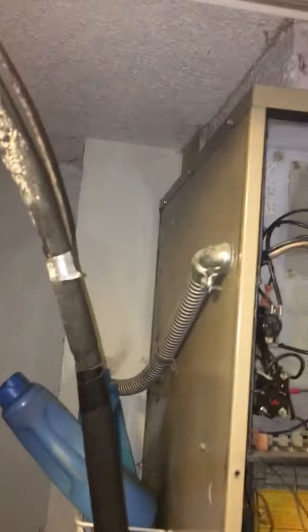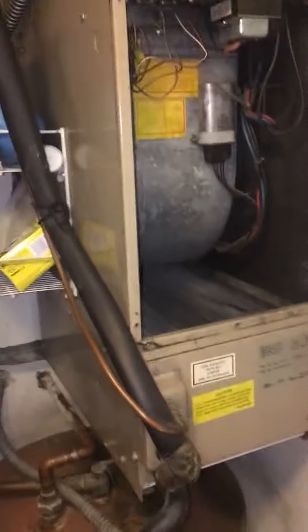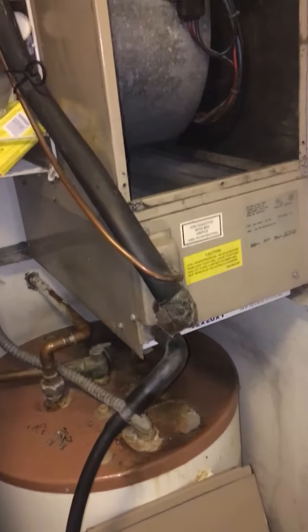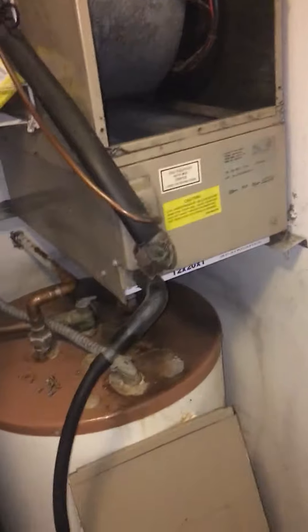It is a 5kw heat strip in here — everything's heated pretty well for them this winter. I don't think they've been through a summer yet, but we'll see what size that unit is and measure everything out so we've got the correct size and efficiency. There's a little bracket underneath. The unit is 40 inches tall.